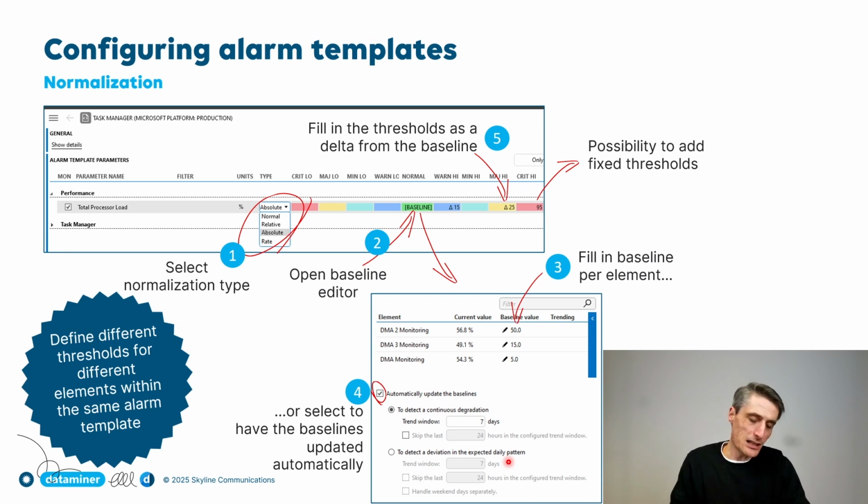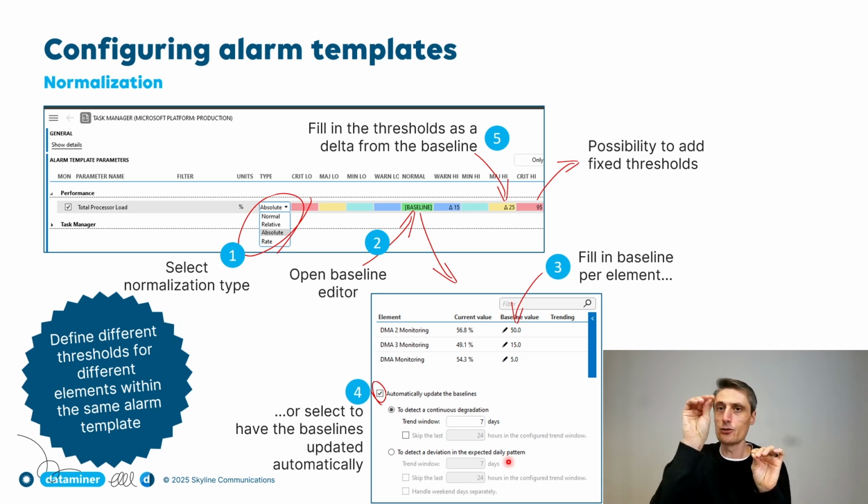So if you take a look at the time now, it will go from the hour until 15 after the hour, and take that 15-minute window and take a look at what was expected during the last 7 days we had in there. So the 24 hours of a day are split up in 15-minute slices, and for every 15 minutes, it will keep track of what the normal expected value is. So it will continuously, after every 15 minutes, adapt the baseline to be what the expected value is, and go up and go down again in the evening to follow.